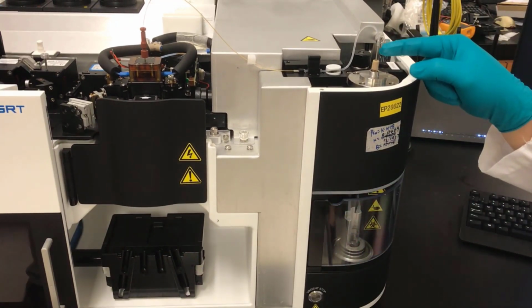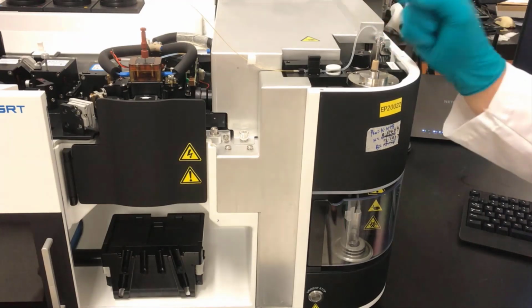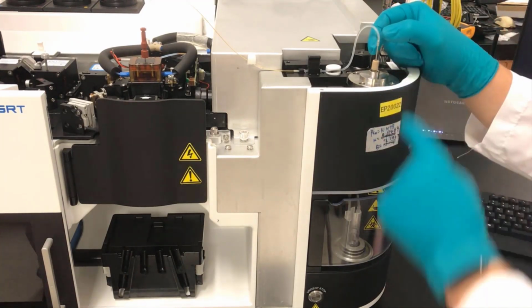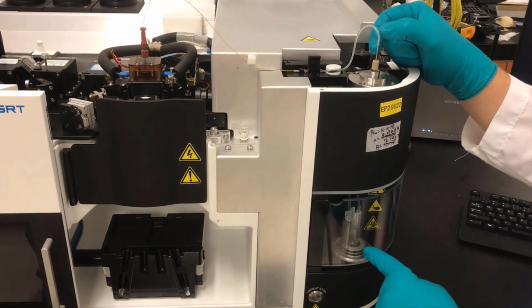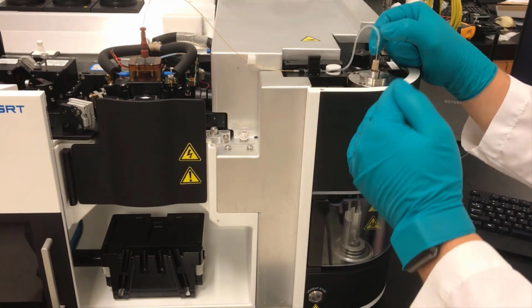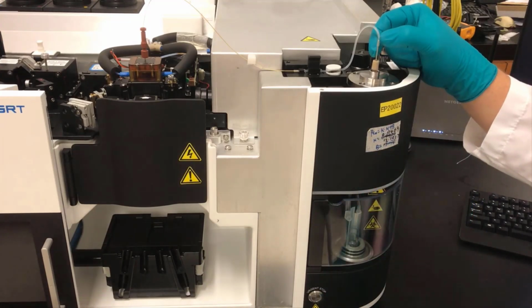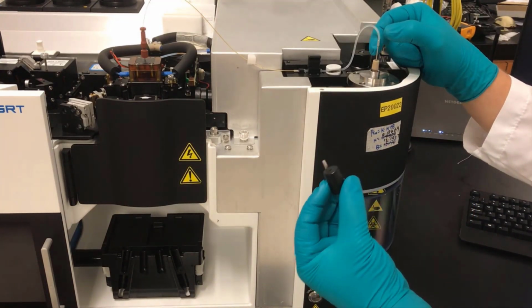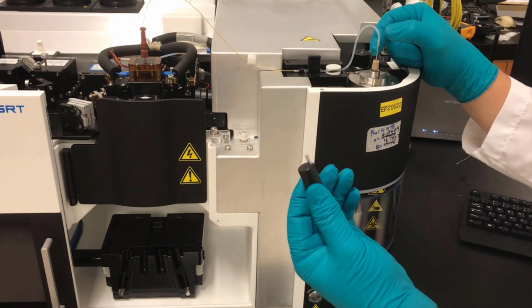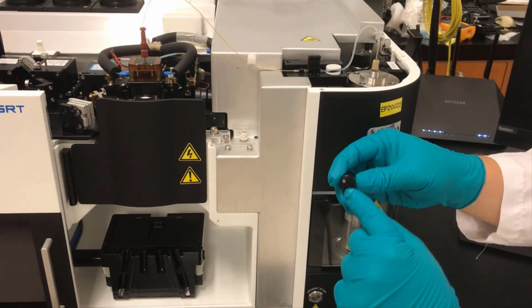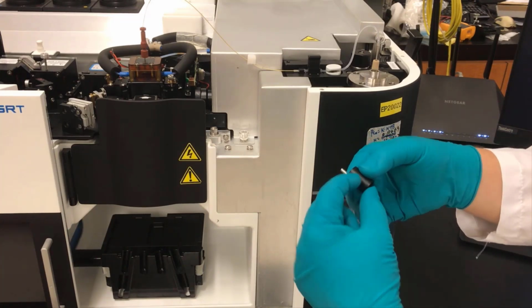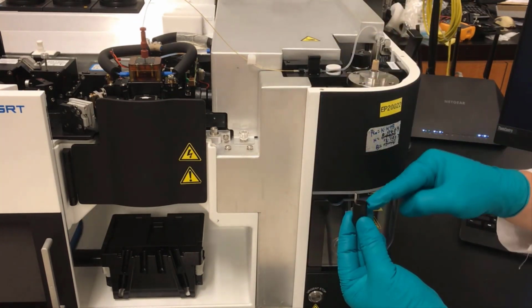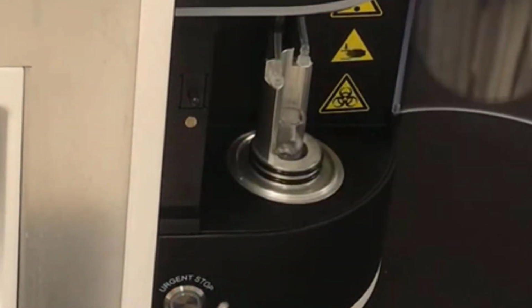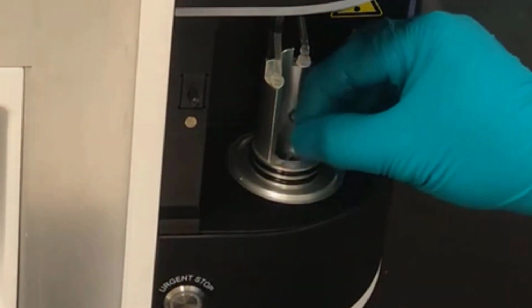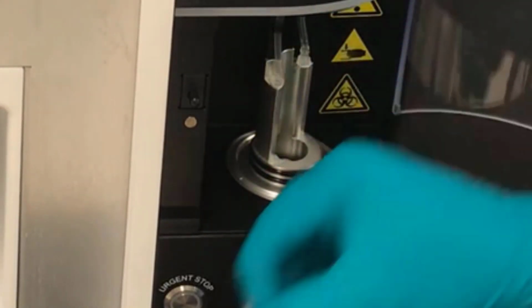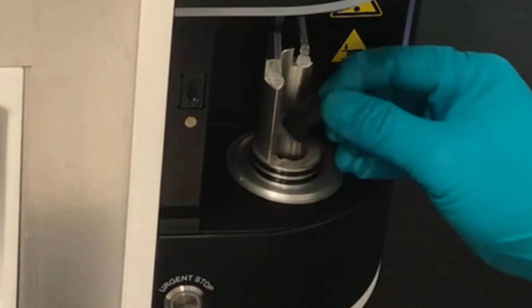The next step in replacing the sample probe is adjusting how deep the probe can go by adjusting the probe's height. Provided in the instrument package is the sample gauge. The sample gauge is used for height adjustment. Open the sample station door. Remove the tube holder from the sample station. Put the sample probe gauge vertically in the tube holder slot.